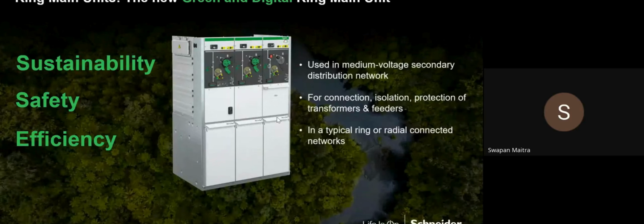So this new design ring main unit is purely digital and manufactured with green premium components, designed for medium voltage secondary distribution networks that offer sustainability, efficiency, and safety. This ring main unit is used for connecting, isolating, and protecting transformers and feeders. As I have already told, it's suitable for both ring and radial network configuration.